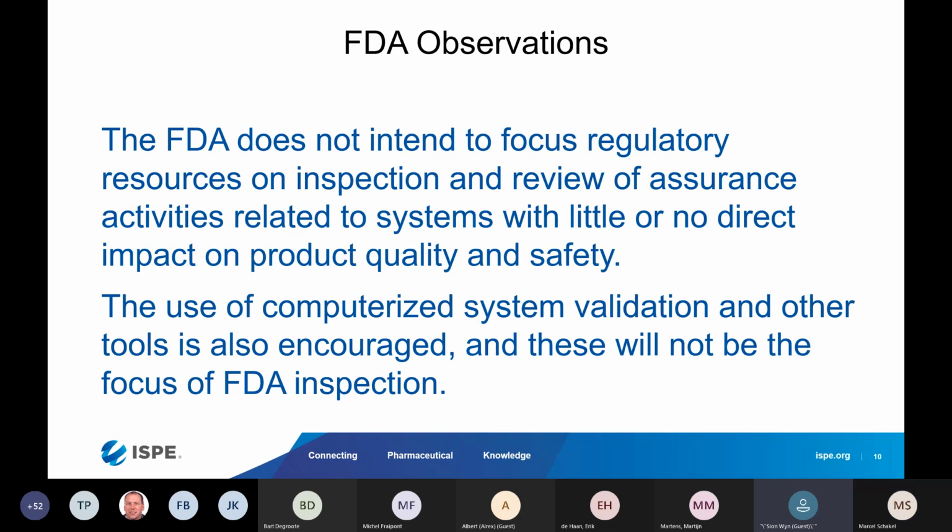I think one way of answering that would be, well, certainly we can follow GAMP guidance and say, right, okay, we need the infrastructure to be qualified. What does that mean? But I think we can use Annex 11 as a good pointer here. Software testing tools should have a documented assessment of their appropriateness, or if I remember exactly the words, the tools we use need to truly support the processes. So if we have decided on a testing process, then we need to use the right tool. We need to install it properly, use it properly, and our personnel needs to understand how to use it. I would definitely avoid the word validation, but it's appropriateness for intended use. The process is the thing.